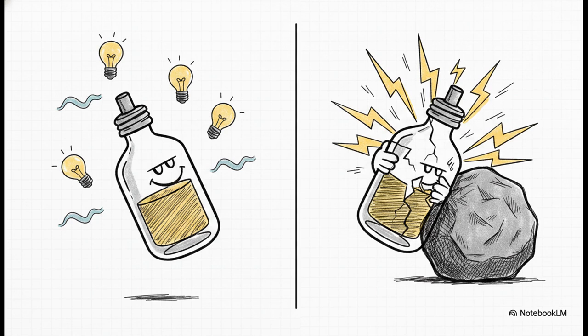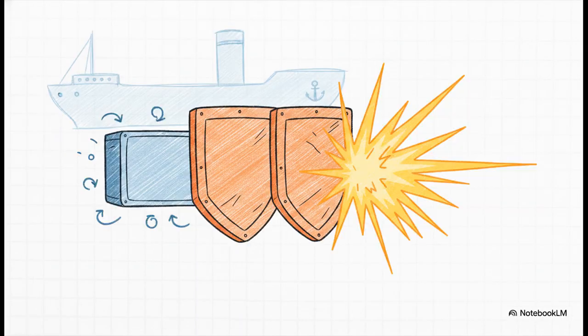raw power. Despite its endurance, the contactor alone only has a 400 amp interrupted current capability with a closing current of 2.4 kiloamps. It is phenomenal at switching normal loads on and off all day long, but it simply lacks the sheer physical mass required to break a massive short circuit current all on its own. And that limited breaking capacity is exactly why fuses are an absolute, non-negotiable requirement in marine applications.